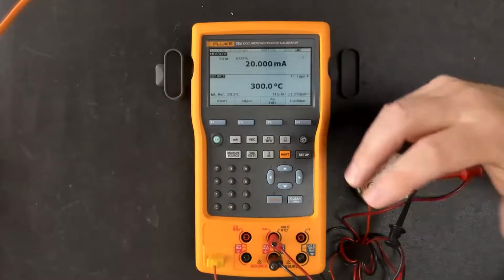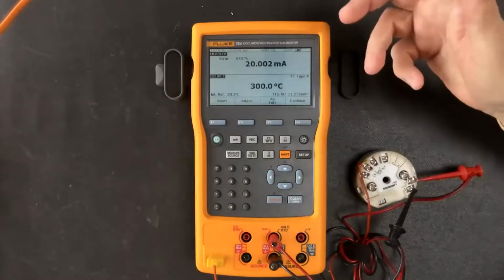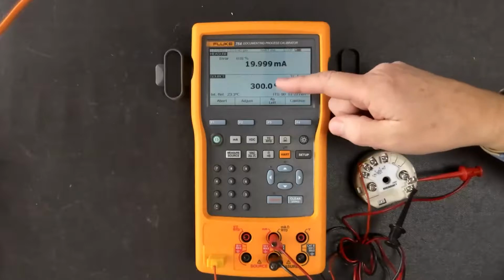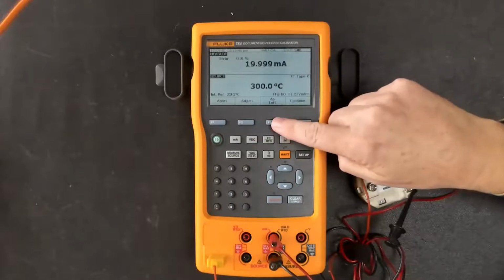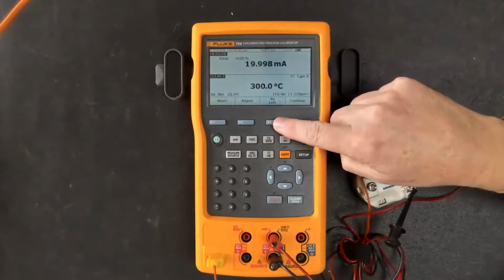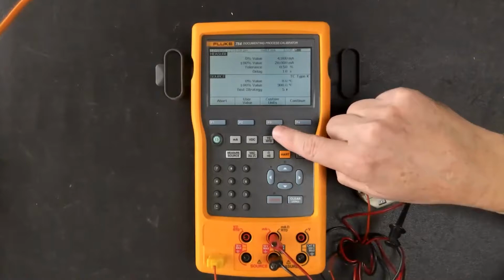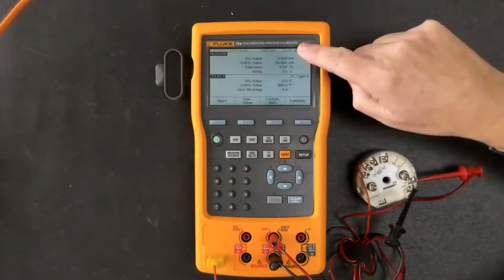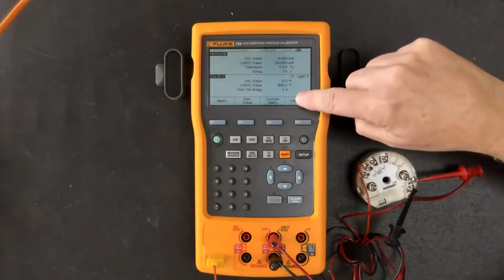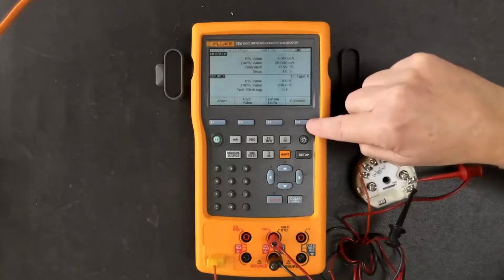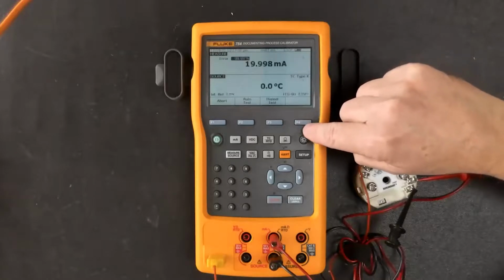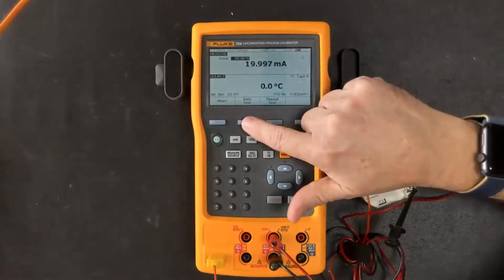So we've done our as found, and we've recorded the readings. We've made our adjustments, and now we're going to perform the as left. So this is as you finish up your calibration. You've done your initial test, you made your adjustments, do the as left. We've got our same configuration information that was downloaded from the software from ProCal here. And then we'll do the Autotest.